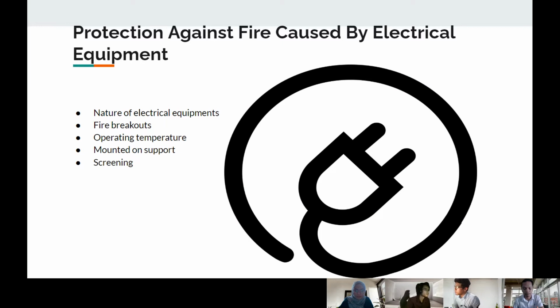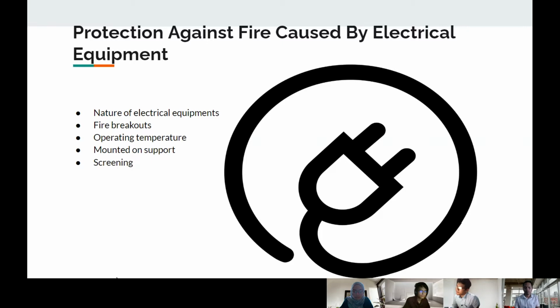First of all, we're going to talk about protection against fire caused by electrical equipment. It is the nature of electrical equipment to generate heat that can cause a fire breakout, and this matter needs to be taken seriously. As an example, if a fire breaks out in a substation, a total breakdown will happen and can affect a lot of customers, with huge losses due to the damage of the equipment. However, we can solve this problem by complying with the installation methods in the IEE wiring regulations. Protection against thermal effect is a must because there will always be a risk of fire.